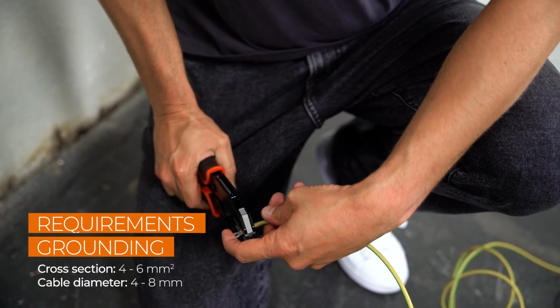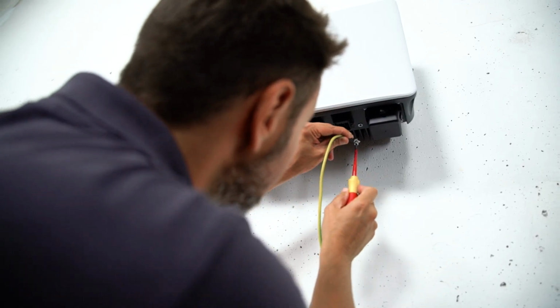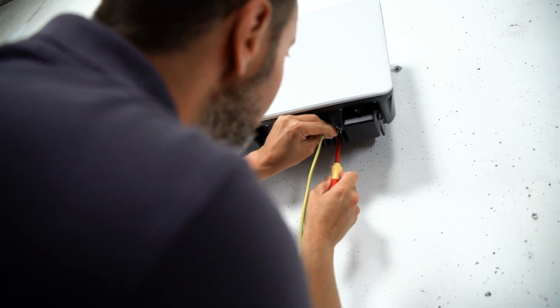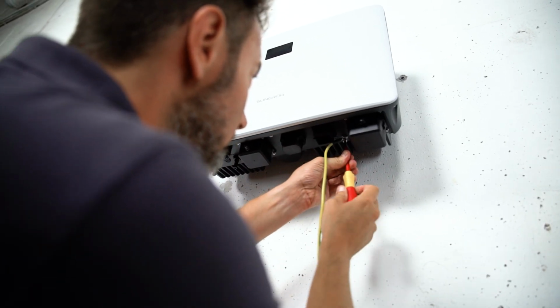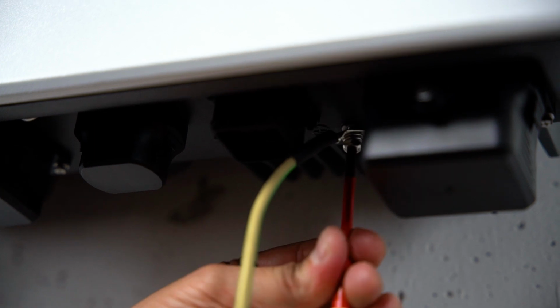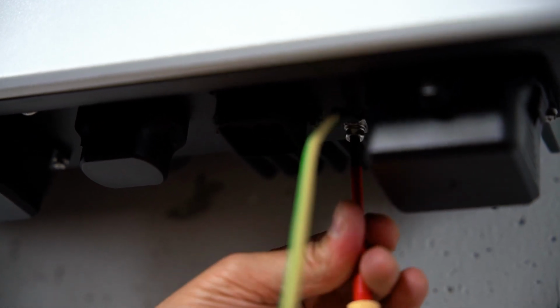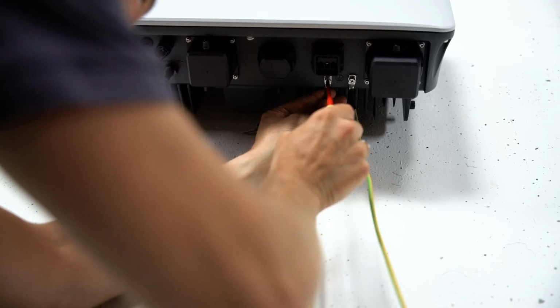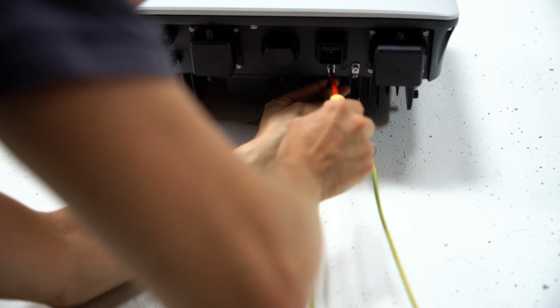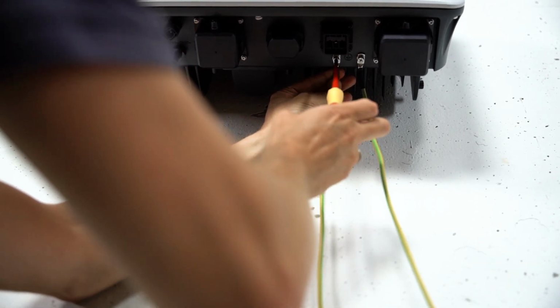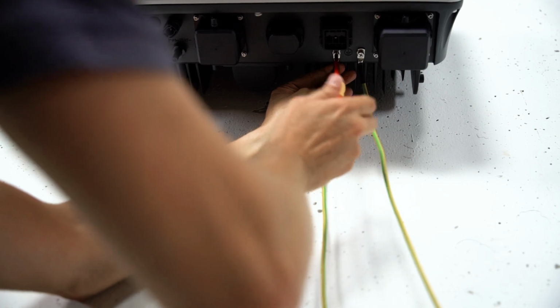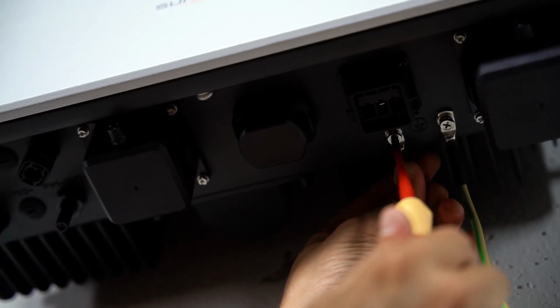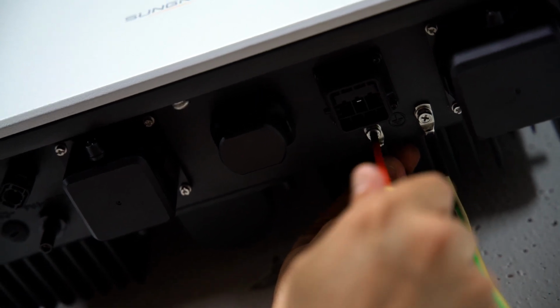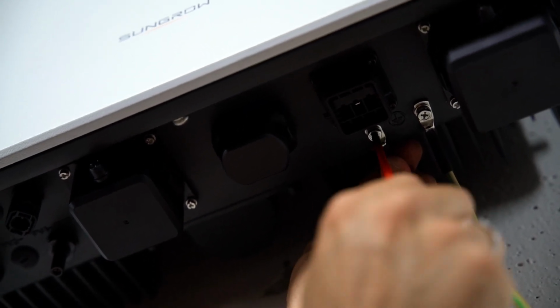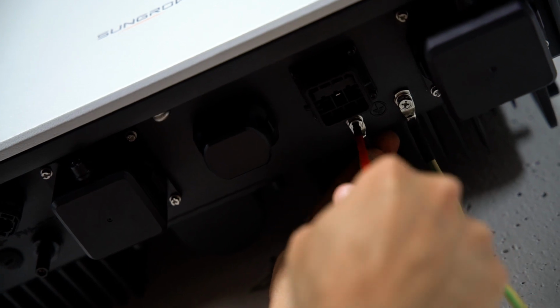In the first step, you have to connect the inverter to ground. There are two PE connections at the bottom of the inverter. The one below the backup port will be connected to the grounding of the backup loads. The other one will be connected to the grounding of the battery. Make sure that the chassis of the inverter, the backup load PE and the grid side PE are all connected to the same grounding point. If the grounding connection isn't done properly, it may affect the backup function.